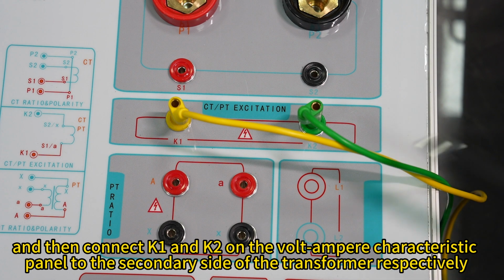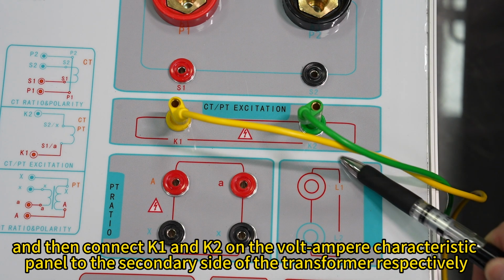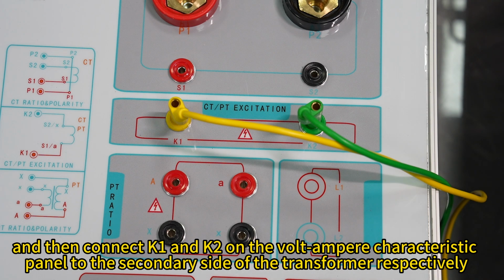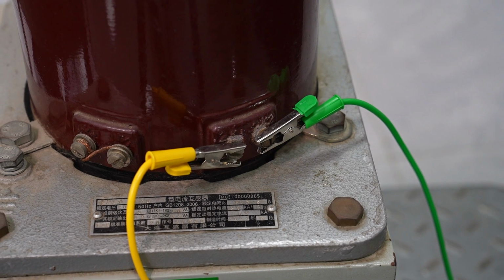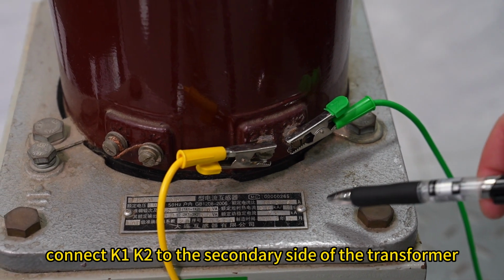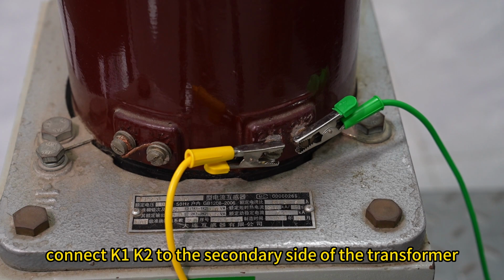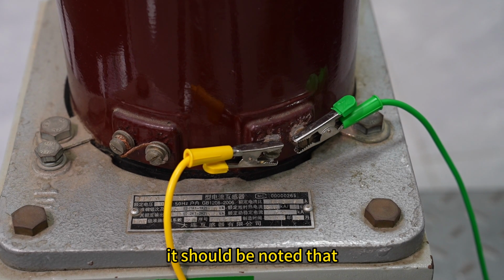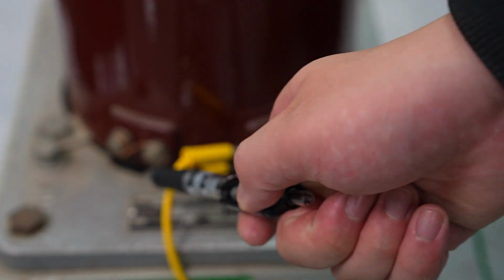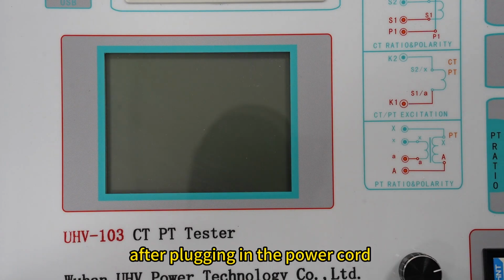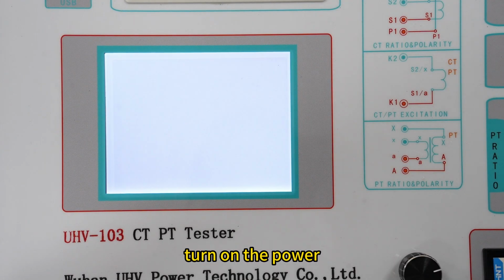And then connect K1 and K2 on the volt-ampere characteristic panel to the secondary side of the transformer, respectively. Connect K1, K2 to the secondary side of the transformer. It should be noted that we did not use one of its secondary terminals, so we need to short-circuit this terminal. After plugging in the power cord, turn on the power.